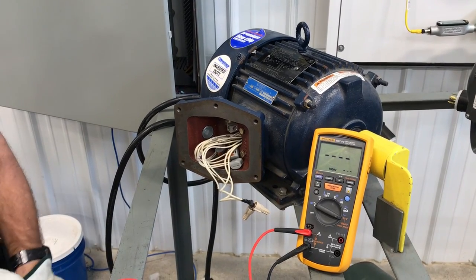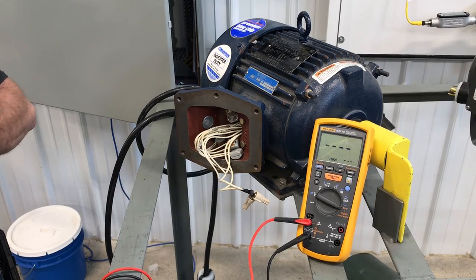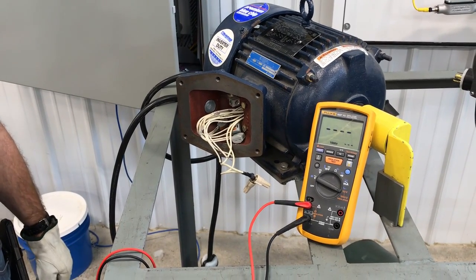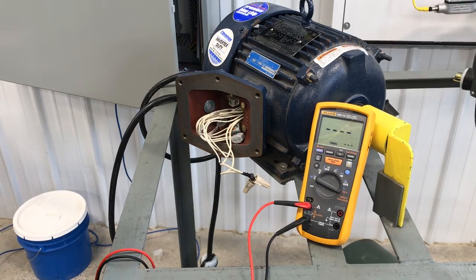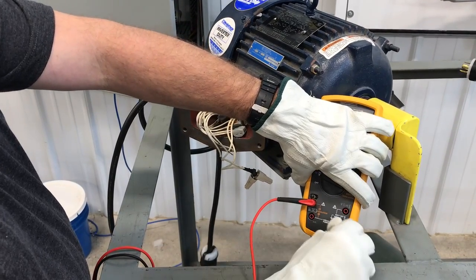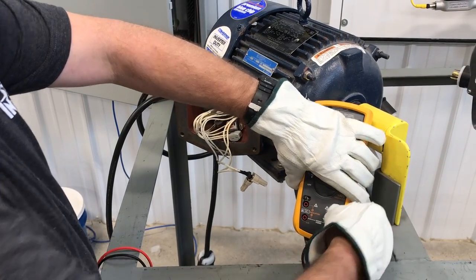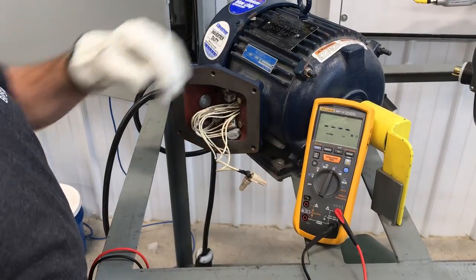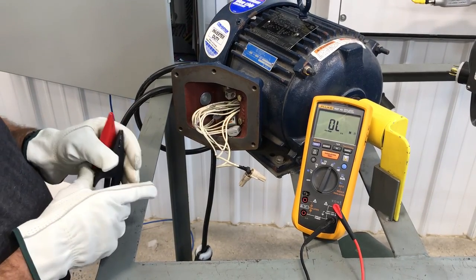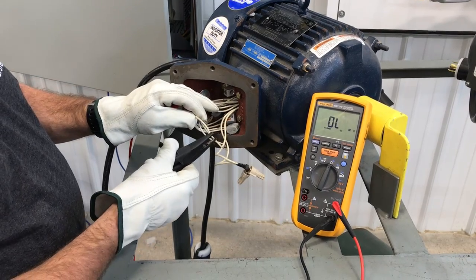Today we're going to run through ohming this motor out. We've got Dan with us and he's going to help run us through this process — we just got done megging this motor. So Dan, what's the process? The first thing you're going to want to do is move your leads over to the ohm side and move your dial up to ohms. We're going to be using the same alligator clips — just makes things a whole lot simpler. We'll put one lead on T1.